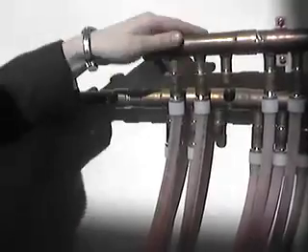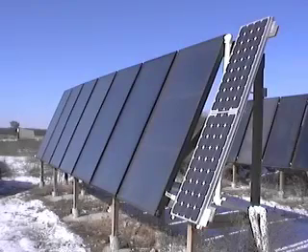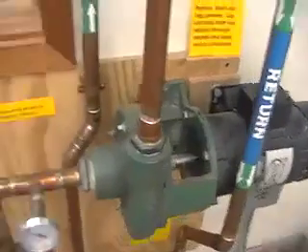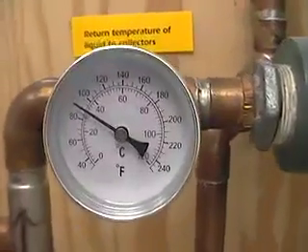Back here in the engine room, we see the solar heat pumped from the collectors outside. The pump is running on 24 volts DC electricity generated by the solar photovoltaic panel mounted with the heat-producing collector. In tune with the power of the sun, glycol from these collectors comes in at 120 degrees and is returned after passing its heat to the floor at 90 degrees.